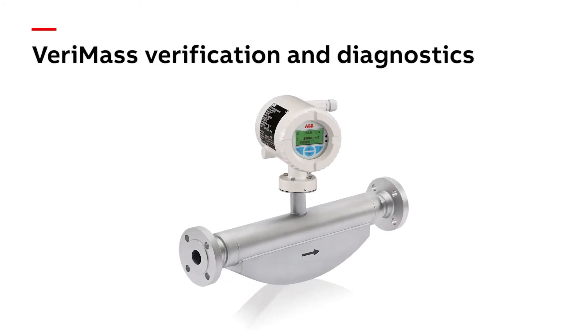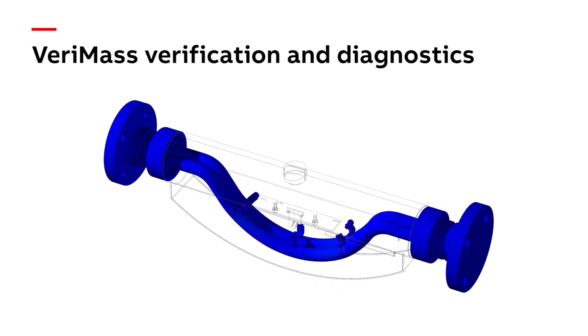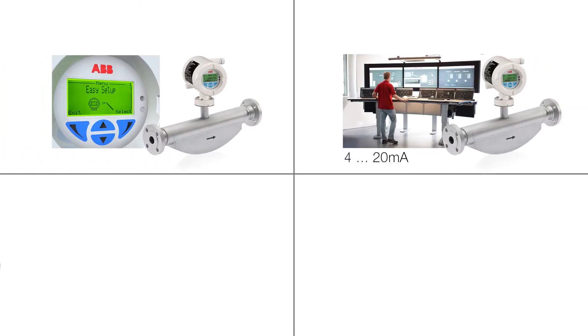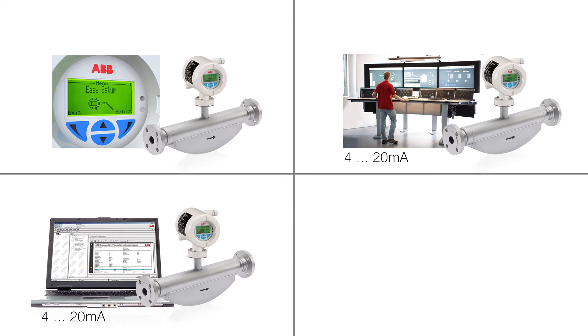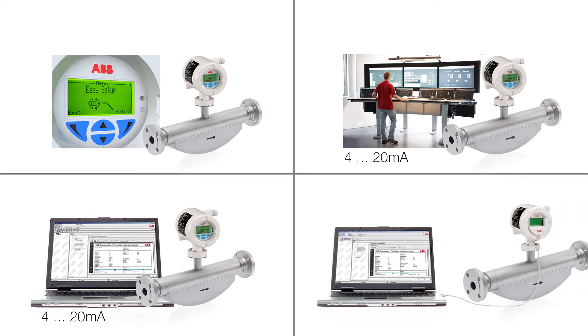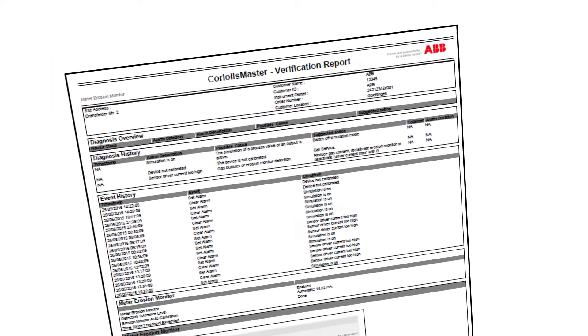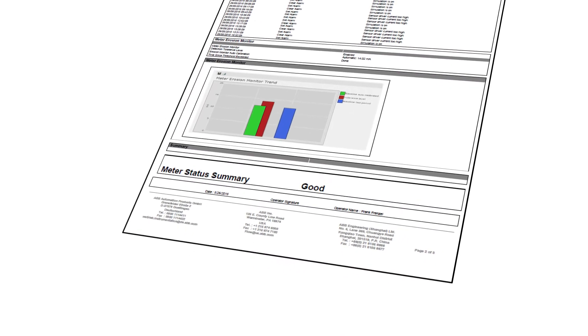The integrated VeriMass verification diagnoses possible tube erosion or coating affecting meter accuracy. VeriMass can be operated through the local display, the control system, or a PC. With the ABB local adapter, the PC can be connected without the need to open the housing. The verification report summarizes the meter status and shows meter trends.